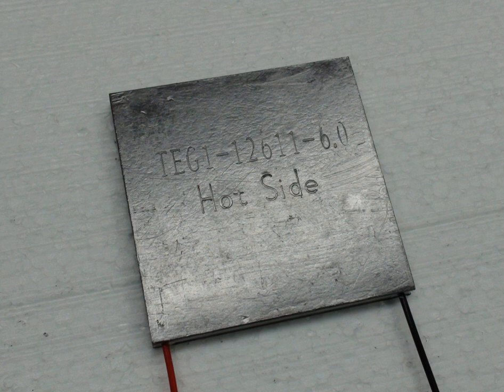The fact that TEC systems are current controlled leads to another series of benefits. The first is that temperature control to within fractions of a degree can be achieved. This accuracy is a result of the device being powered using standard DC current, allowing the user to adjust exactly how many electron-hole pairs are recombining and, therefore, how much heat or cooling is being produced.